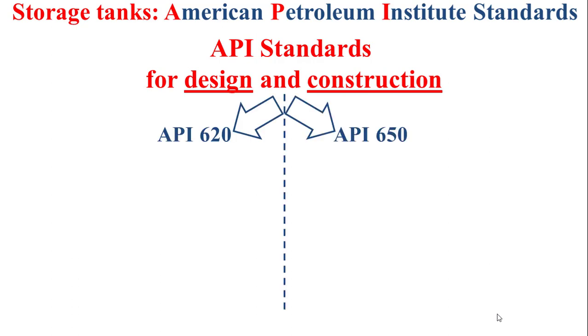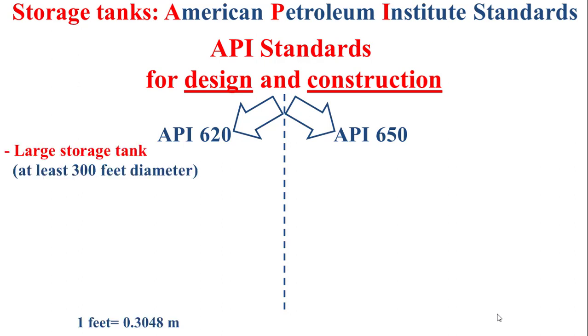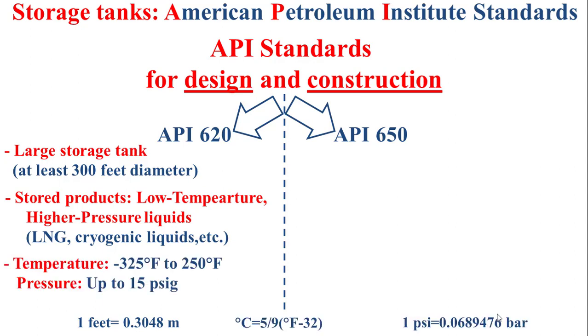Now for the American Petroleum Institute API standards associated with the design and construction of storage tanks, we have the API 620 and the API 650. The API 620 is associated with large storage tanks — large meaning at least 300 feet in diameter. The stored products are principally low-temperature, higher-pressure liquids such as liquefied natural gas (LNG) and cryogenic liquids. The operating temperature is between minus 325°F to 250°F, and the operating pressure is up to 15 pounds per square inch gauge.